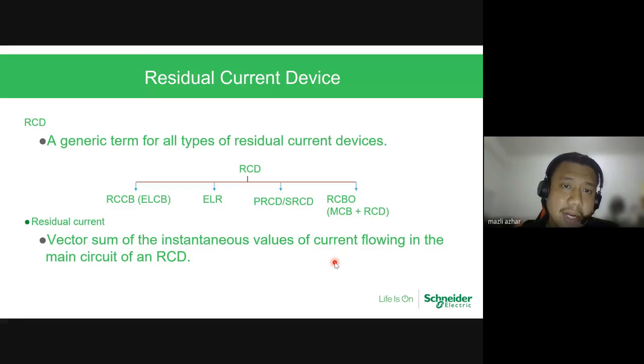So let's talk about RCD, it's a generic term actually. It can be divided into 4 or 5. You can see that as the RCD, you will have an RCCB, or the old term we call ELCB. If you go to any of the electrical stores now, they will still talk about ELCB. So ELCB is the old term. The new term they call RCCB. ELR, normally used for high power.